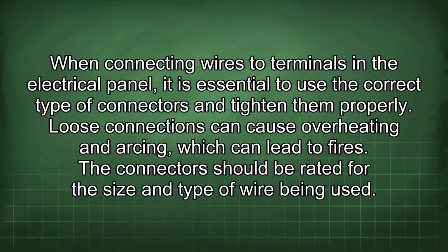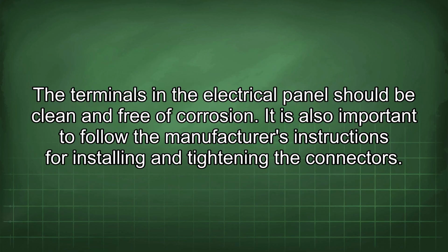When connecting wires to terminals in the electrical panel, it is essential to use the correct type of connectors and tighten them properly. Loose connections can cause overheating and arcing, which can lead to fires. The connectors should be rated for the size and type of wire being used. The terminals in the electrical panel should be clean and free of corrosion. It is also important to follow the manufacturer's instructions for installing and tightening the connectors.